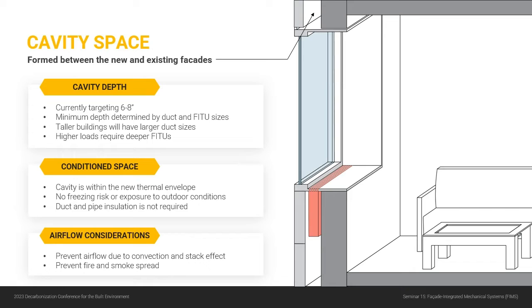And the other thing driving this dimension is the size of the FITU. So if you have a space with higher loads, you might not be able to get that capacity out of a narrow 6-inch unit. You might need to beef it up a little, and that's another thing that can drive you closer to an 8-inch cavity depth.